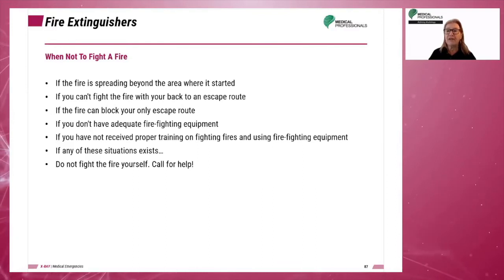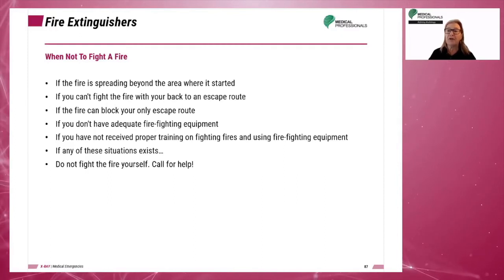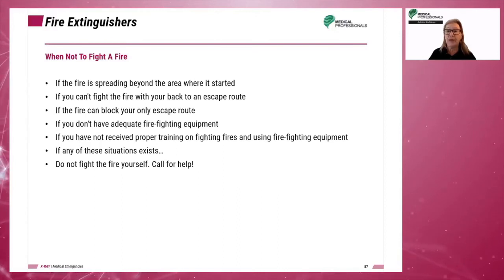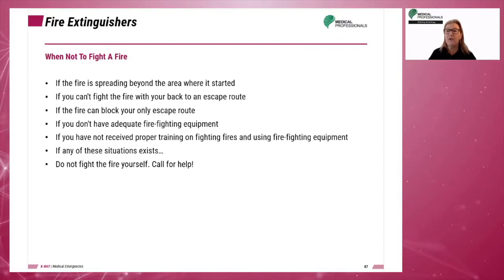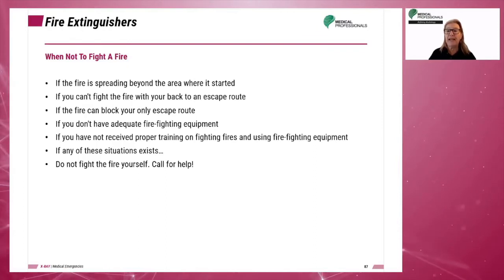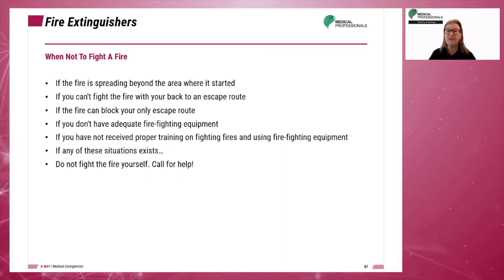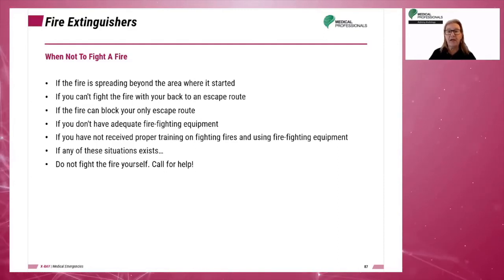Do not try to fight a fire if the fire is spreading beyond the area where it started, if you can't fight the fire with your back to an escape route, if the fire can block your access to the escape route, if you don't have adequate firefighting equipment, or if you have not received proper training on fighting fires and using firefighting equipment. If possible, do not try to fight a fire by yourself — get help.